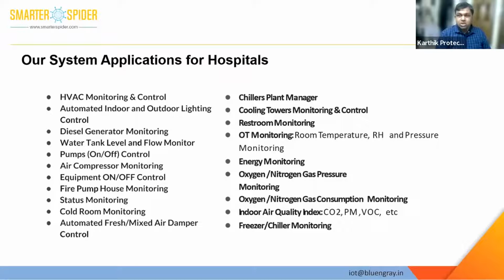So, applications for hospitals and healthcare. We have HVAC monitoring and control, automated indoor and outdoor lighting control, diesel generator monitoring, water tank level and flow monitoring, pumps on/off control, air compressor monitoring, equipment on/off control, fire pump monitoring, status monitoring, cold room monitoring, automated fresh or mixed damper control, your chiller plant manager, cooling tower monitoring and control, and restroom monitoring. In OT monitoring, we have room temperature, RH and pressure monitoring, energy mapping, oxygen or nitrogen gas pressure monitoring, then your consumption, indoor air quality index like CO2, PM, VOC levels, etc., and freezer or chiller monitoring.